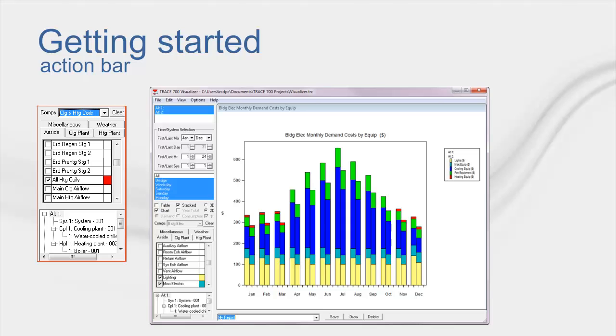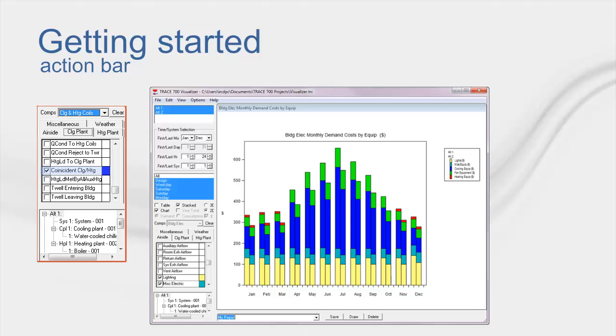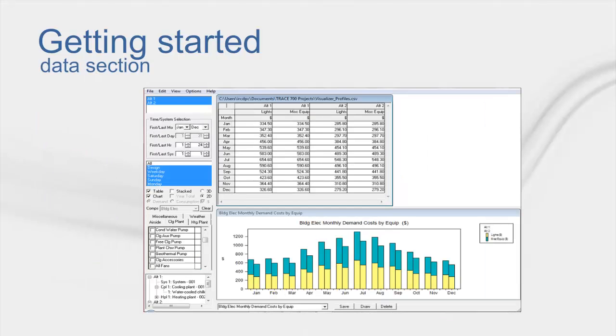Lastly, as an example, if you frequently model water source heat pumps, you know that Trace does not have a report that shows coincident heating and cooling. Well, you can set up a custom report to have that variable and others to give you all the applicable information you need to review your water source heat pump in one comp.